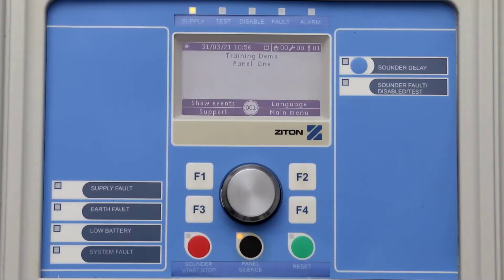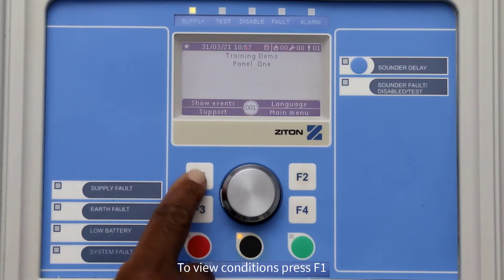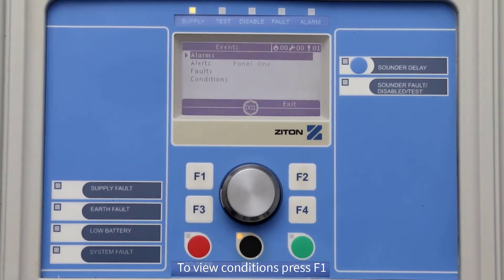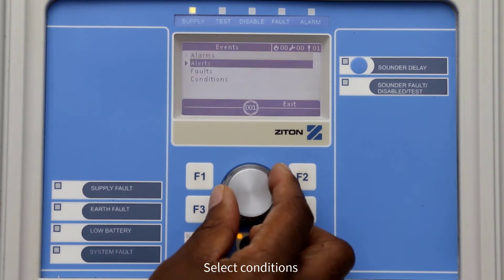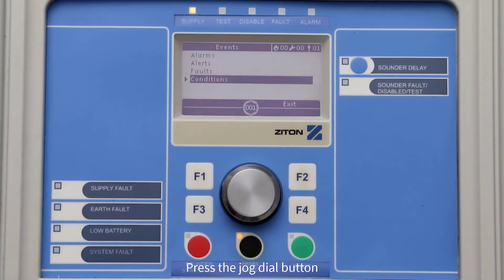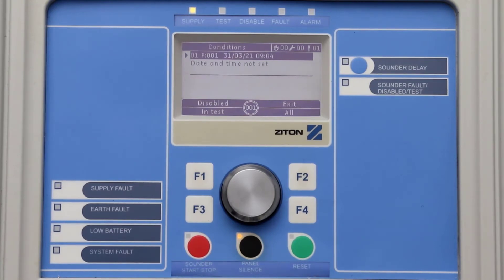There are reasons when sometimes you may have to amend the time and date on your fire alarm panel. For example, every time a panel is powered down, the panel will always display a condition. You can view the panel conditions by pressing F1 to select show events. Using the jog dial button, turn the button to select conditions, then push the jog dial button. As you can see, the date and time is not set.